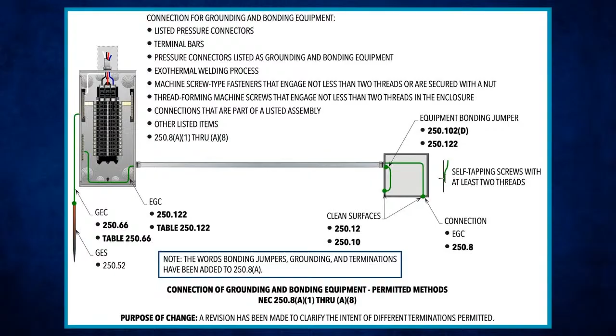I do want to tie in some of my myth of the week. King James will probably get mad at me for this, but a lot of people say you can't install a ground lug without scraping the paint. We proved this - it was probably 2 years ago - that you don't have to scrape the paint. Do they scrape the paint when they put a ground bar in an Eaton panel? No, they just need that 2 threads of contact. So these code loops that King James tosses in there end up canceling out a lot of the myths we've been covering. It's kind of cool that I can go through and show how this all ties in. What does it say?